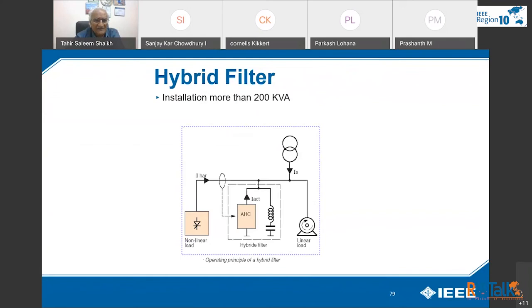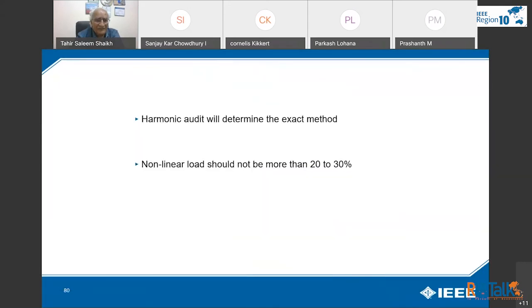And for installations of more than 200 kVA, a hybrid filter. It is a combination of an active sine filter as well as a passive filter. Whatever remains with the active sine filter, this hybrid filter will correct with a sensing device to create the same harmonics, which will nullify the impact of the harmonics on linear loads. So this is for installations of more than 200 kVA. Whenever you have to decide, a harmonic audit will determine the exact method. As a general practice, non-linear loads should not be more than 20% of a transformer or generator.